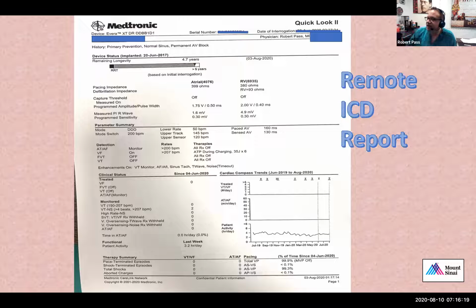But if you have capture management on, or capture threshold, then the device can measure it and set the output much lower than double. It could set it, let's say, 1/4 of a volt above it, or 1/2 a volt above it instead of double. And theoretically, that could save battery life over the course of the device. Generally, I don't usually turn that on because in most patients, if the lead has good low thresholds, the amount of benefit or savings is fairly minimal from turning that feature on.